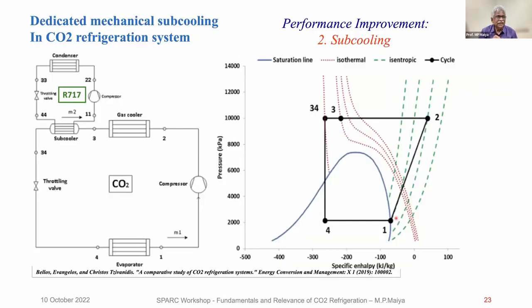The other method is to have dedicated mechanical subcooling. Here you have 40 degrees centigrade at the gas cooler, and you can cool to 30 degrees centigrade by using a separate system. This cooling is very simple and easy, because efficiency is higher, COP is higher, since you're cooling almost near ambient temperature. But when you throttle, you will get the same amount of cooling at a much lower temperature. You will magnify it. By second law efficiency, you will improve substantially. So this is a simple trick you can use to improve the efficiency.